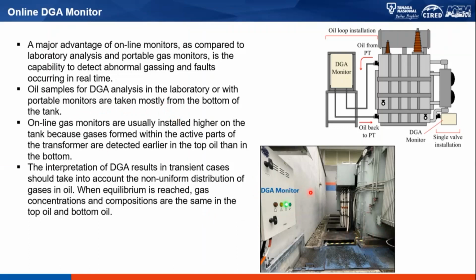But for online monitors, it is more practical to connect it from the top going down to this monitor and going back to the bottom, because as we are talking about gases being generated here, there's a tendency they will rise to the top instead of going to the bottom. So it will be more logical to install this monitor coming from the top and going back to the bottom.